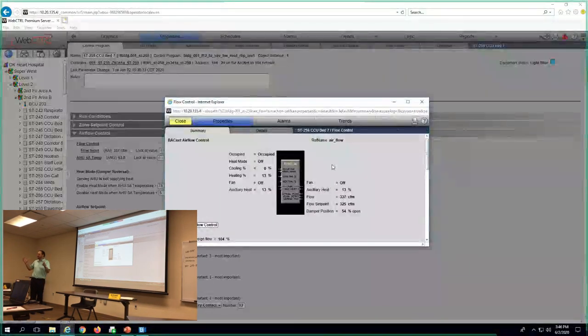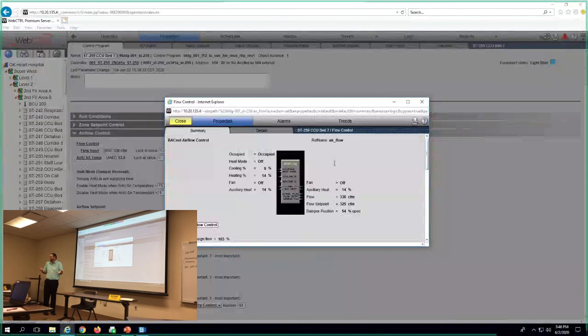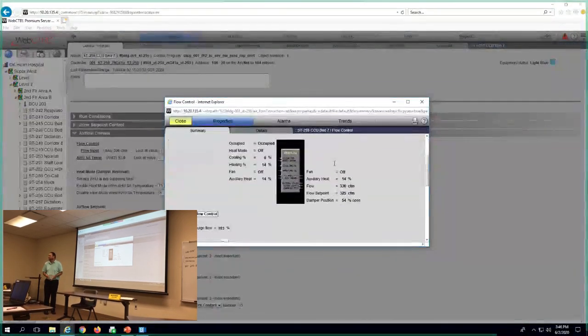If we're trying to keep the pages easy to read and easy to diagnose problems, the real data and a lot of the information you want to drill down and troubleshoot is on these properties pages, the IO pages, the logic pages, kind of behind there. You can populate these pages with all this data, but there's no point if you're never going to use it. Some of these VAVs you may never look at unless there's an issue with it. But if there's an issue, where do you go to find what's going on? So you can click on this airflow control.